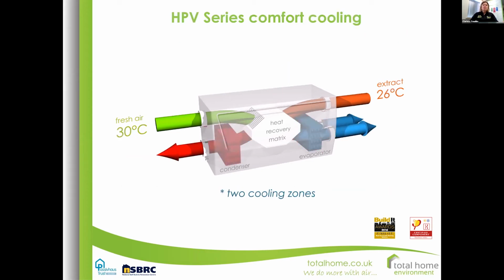And with cooling, those temperatures, again, we've obviously changed it to be a bit like the summer, so 30 degrees outside and perhaps 26 being extracted from the house itself. And with that amazing energy efficient refrigeration cycle, you've reversed the heat pump, and instead of providing heat, it's providing cooling, and we can perhaps supply the air in bedrooms and living rooms at between 10 and 15 degrees. Now, don't get me wrong, this isn't like air conditioning. You're not going to get 20 or 30 degrees difference in temperature, but you will get maybe 5 to 10, which can be the difference between a good night's sleep or not. So you can see the potential here for comfort and keeping those temperatures within the house below that 10% that I spoke about earlier.